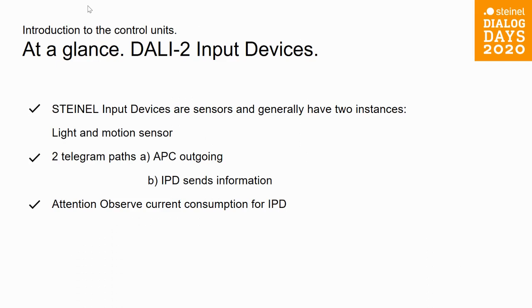STEINEL input devices are sensors and generally have two instances, light and motion, with the exception of the dual light sensor, which has two light sensors, and the dual tech with several motion sensors. We have two ways of reading sensor values: the targeted polling of the application controller and the event messages, which is determined by the DALI bus. Specification of the guaranteed supply current for DALI-2 power supplies. A ballast is defined as 1 participant in terms of current consumption, 2 milliamps.